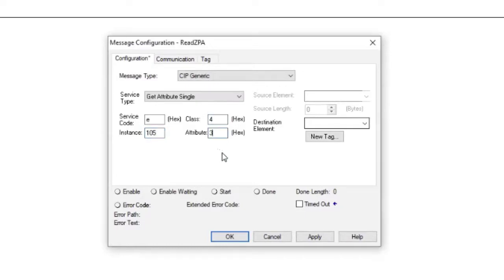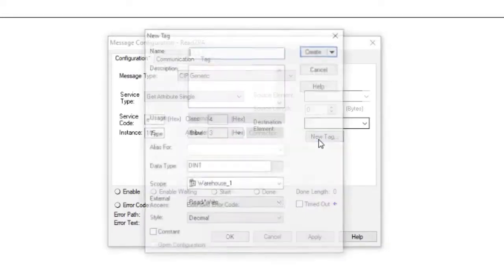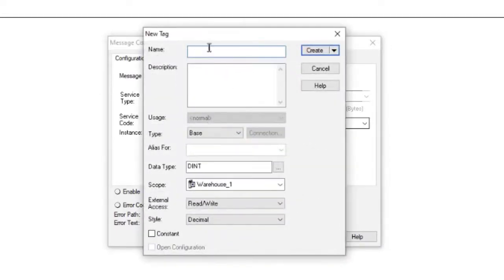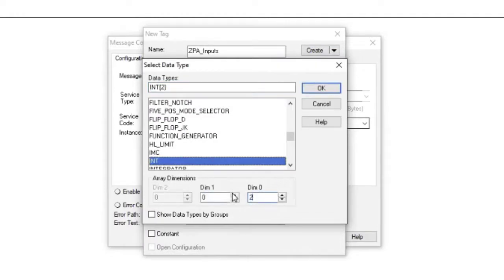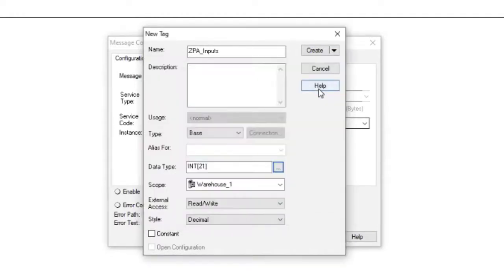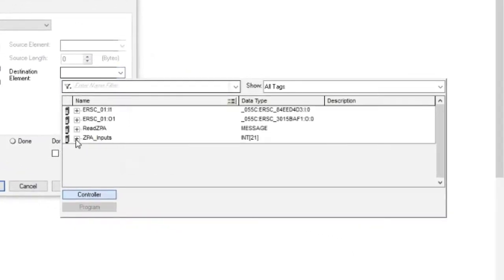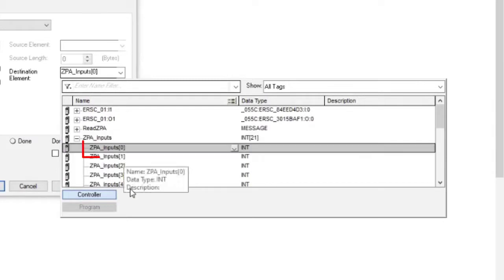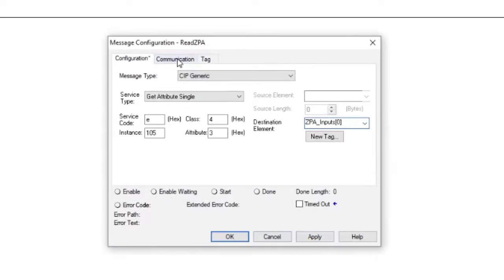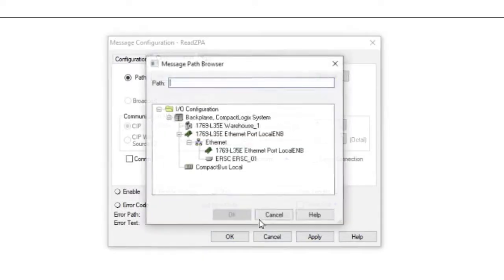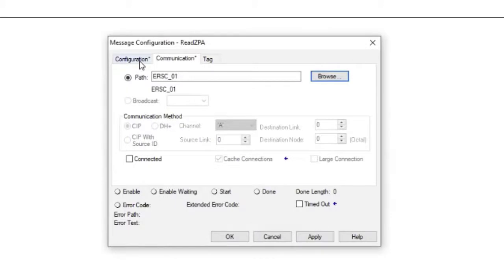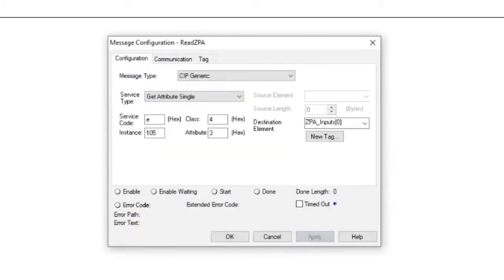The class is 4 and the attribute is 3. Now let's create the tag we want to put the data into. Type in the name and create the tag with the data type integer and then make it an array with 21 elements. When you select the destination element, be sure to select the first element of the array. The data from instance 105 will populate the 21 elements of this array. On the Communications tab, select the ERSC from the Ethernet tree, click Apply and OK, and then you're done.